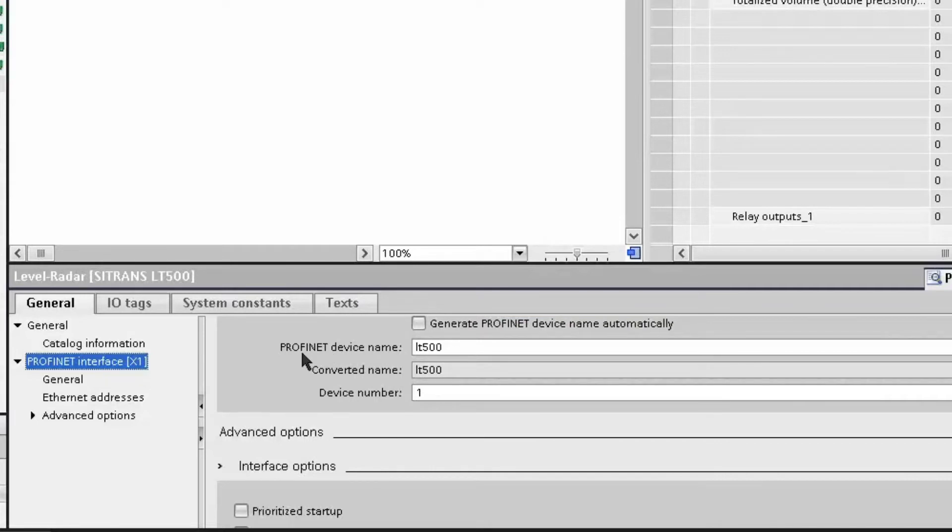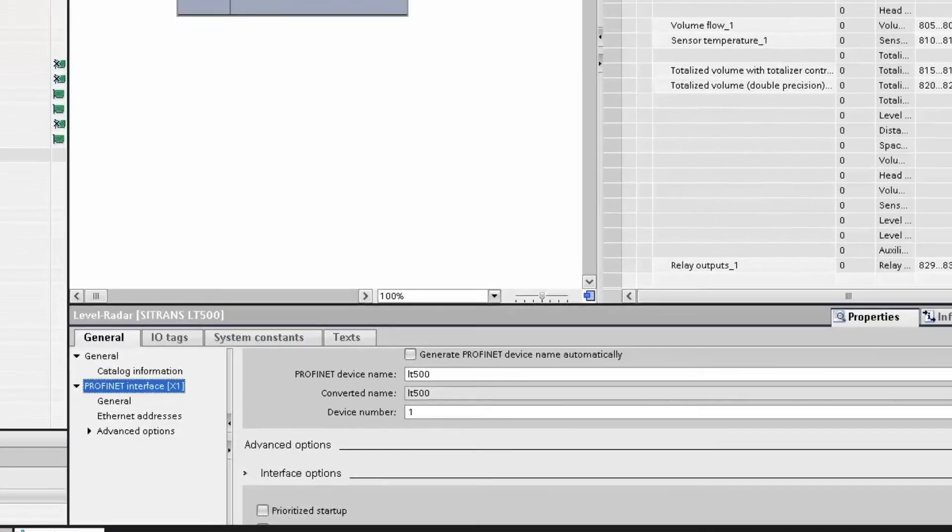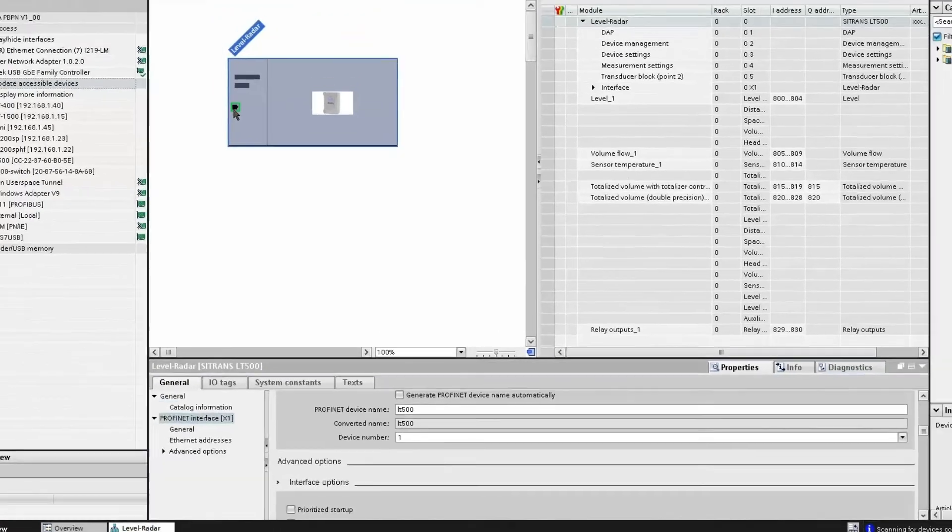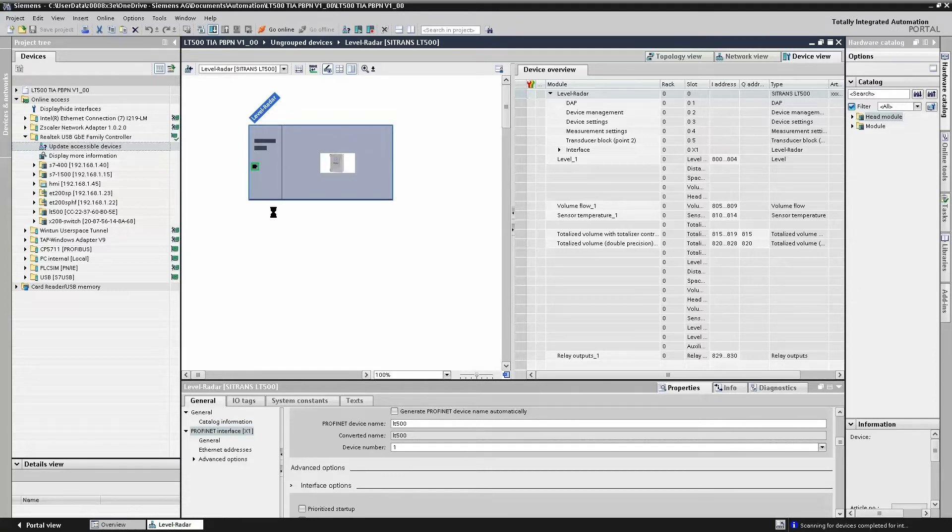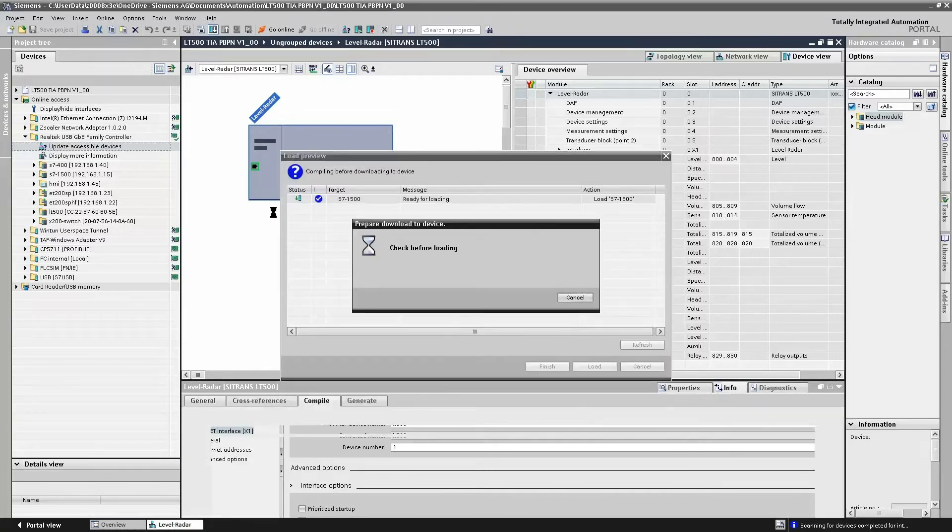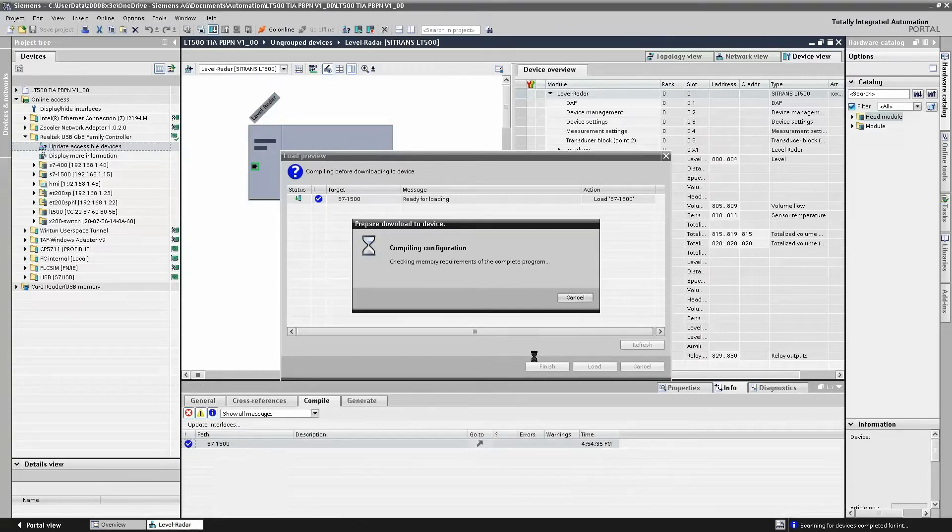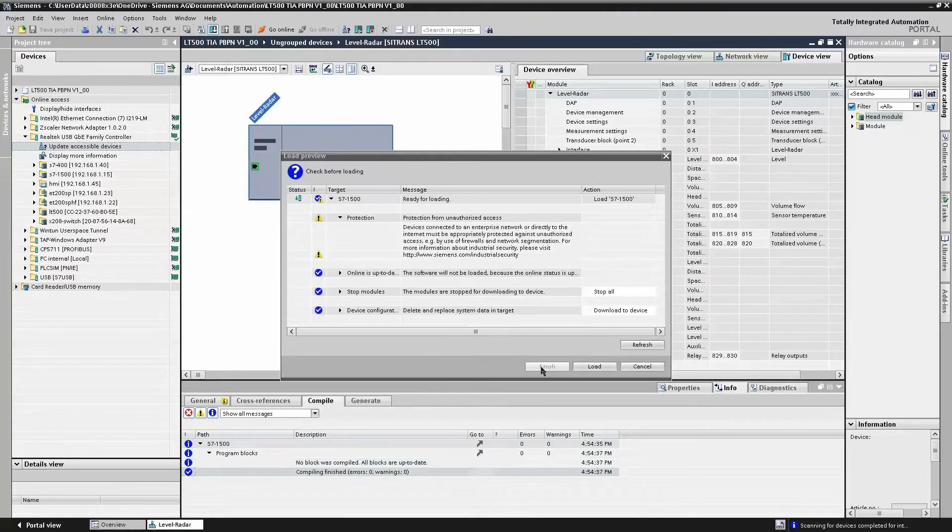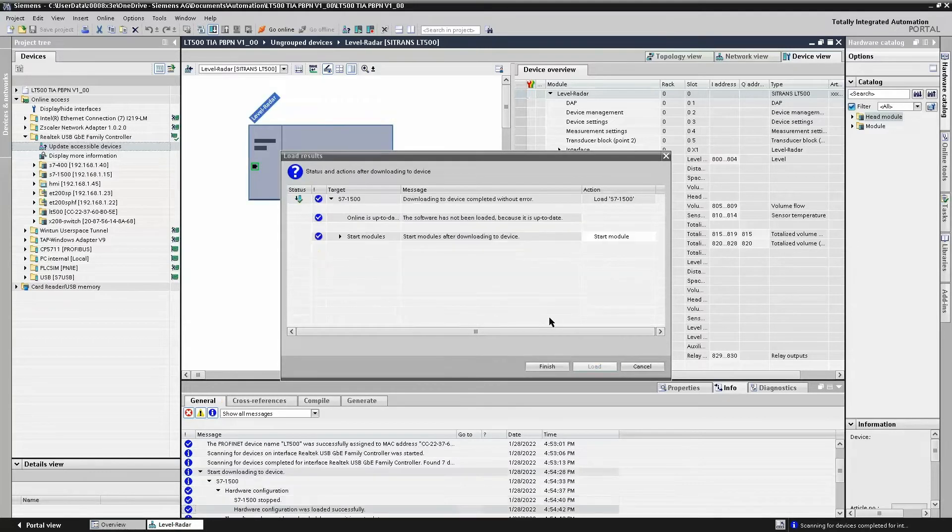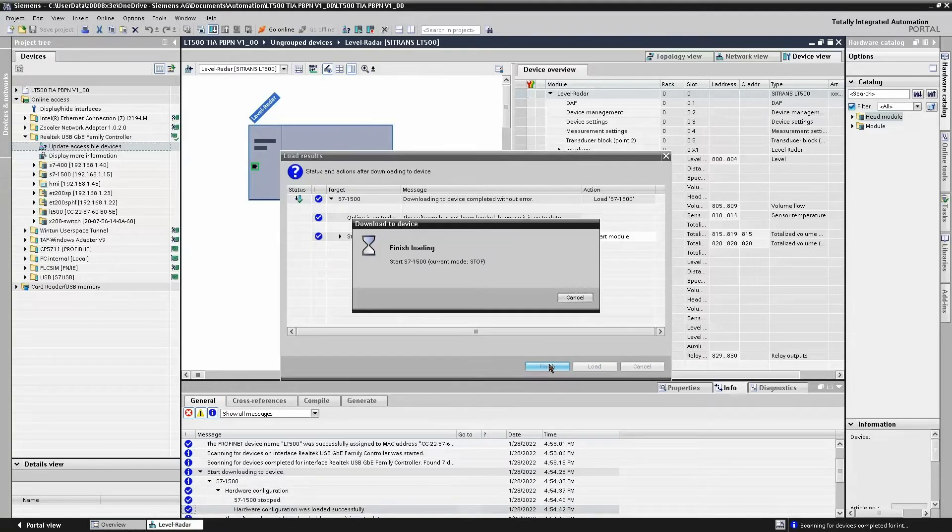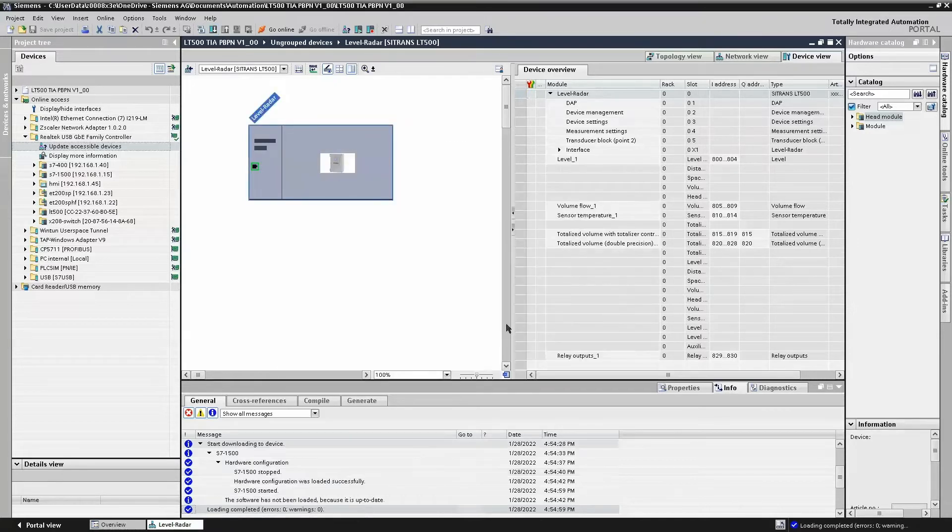So here we've given it the name of LT500. This device name will be used by the IO controller. All we need to do to get our system up and running is to download to the IO controller. The IO controller will use the device name from our project. Once downloaded to the IO controller, the IO controller will then attempt to look for the Sitrans LT500 via its device name. Once it finds the device name, it will then assign the IP address.